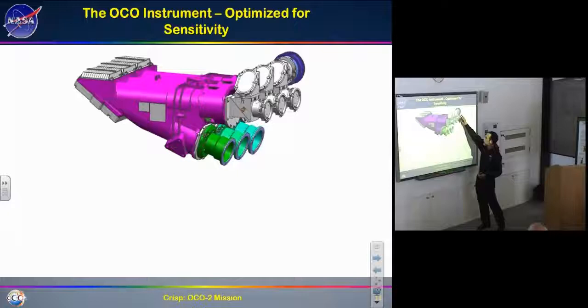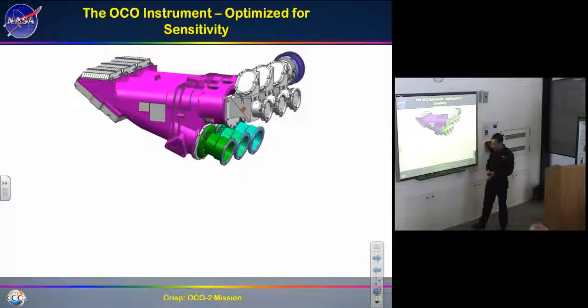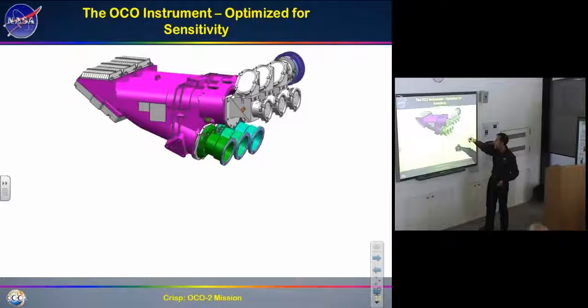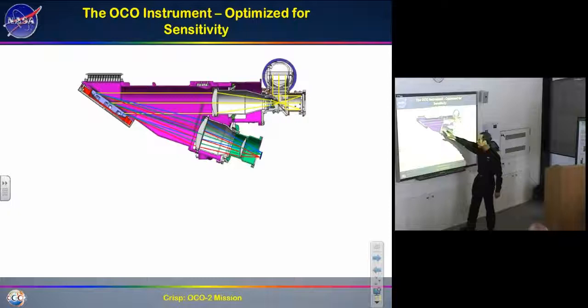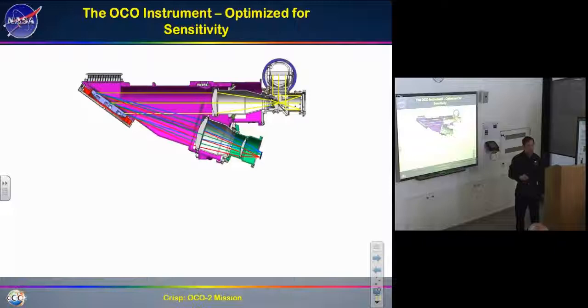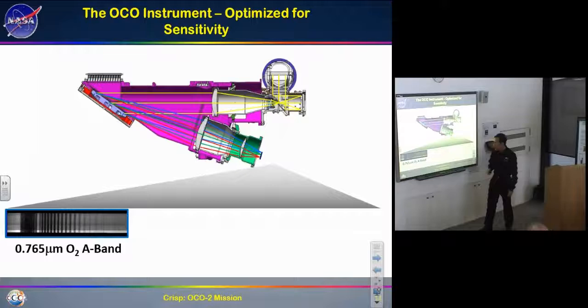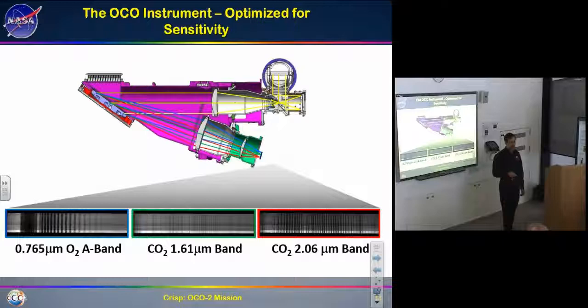The instrument is a three-channel grating spectrometer — three spectrometers stuck together with a common entry telescope. There are three channels: one for CO2 near 2 microns, one at 1.61 microns, and one at 0.76 microns for oxygen. It uses a simple grating spectrometer design — light from a telescope goes through a narrow slit, a collimator, hits a plane grating, and gets imaged onto a two-dimensional imaging sensor. This produces high-resolution spectra of the oxygen A-band, the 1.61 micron CO2 band, and the 2.06 micron CO2 band.